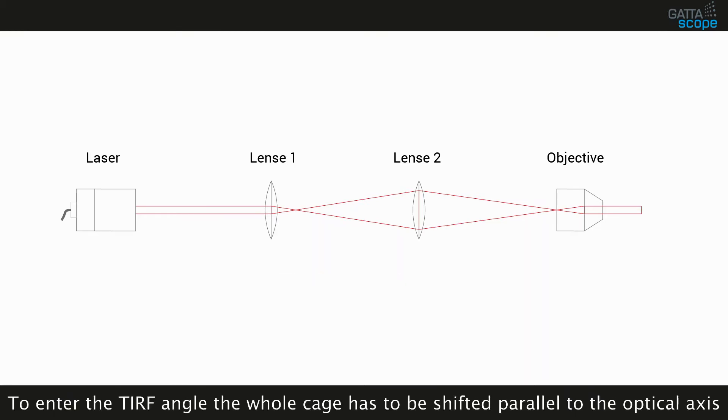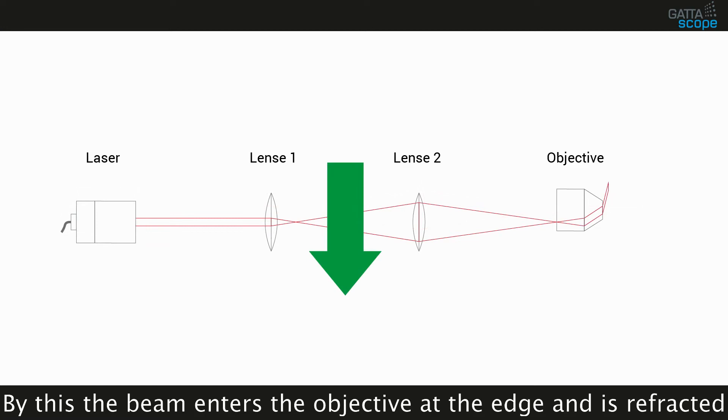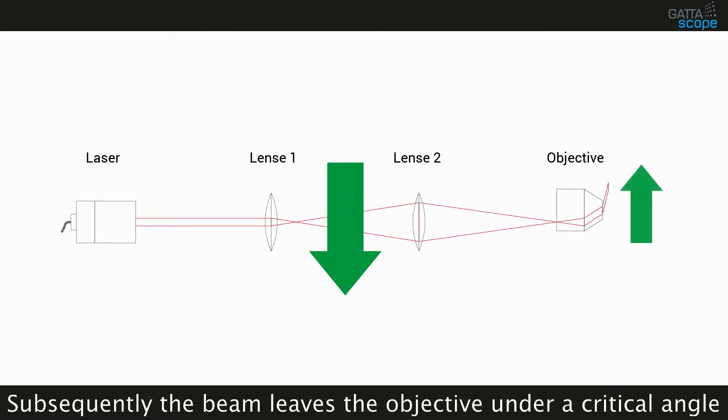To enter the TIRF angle, the whole CAGE has to be shifted parallel to the optical axis. By this, the beam enters the objective at the edge and is refracted. Subsequently the beam leaves the objective under a critical angle.